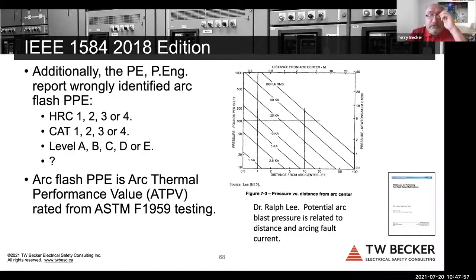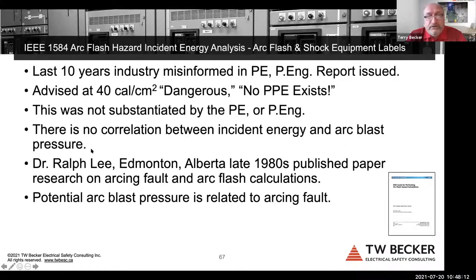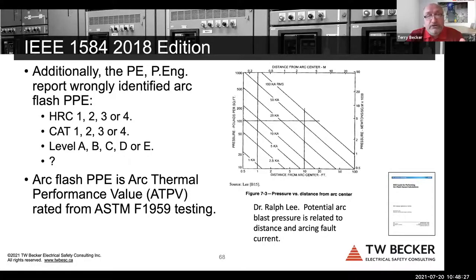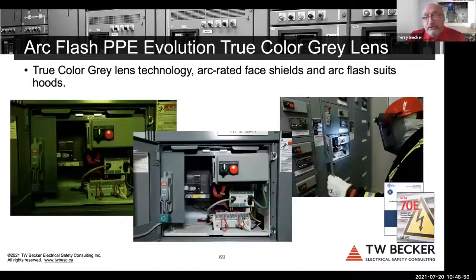And I pointed people, I said, this is published in an IEEE standard, the Yellow Book, that incident energy doesn't correlate, right, to arc blast pressure. It correlates to arcing fault current, right? So it never correlated. So 40 calories is not a dangerous incident energy level, and it's a false statement that no PPE exists, because again, Oberon company has an arc flash suit up to 140 cal ATPV. All right, so there's no correlation. We need to continue to work that out and ensure engineers' reports don't include any information about this. And the reports, again, don't include a HRC number, a category number, a level letter. There's no correlation between, again, the arc flash PPE category table method and incident energy calculations. And I need to continue to make sure that the software that's used out there doesn't continue to exacerbate this problem, all right? Arc flash PPE evolution, just quickly, again, I'm running short on time.